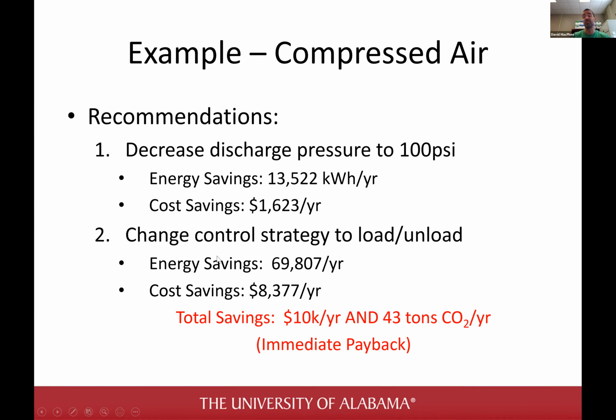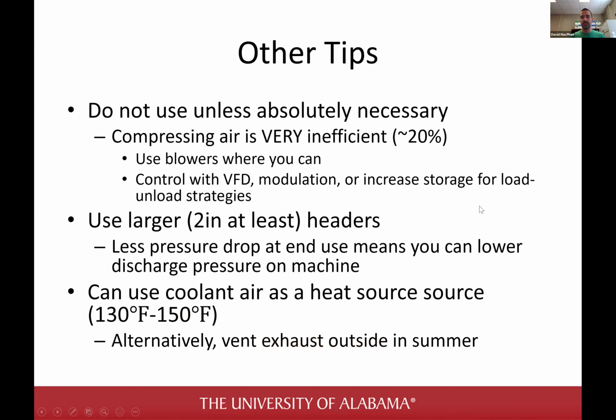Decrease discharge pressure, change control strategy. Another thing is decrease the leaks. Now, without seeing the facility, I can't really tell you how many leaks your facility has. There are a lot of facilities that have basically no leaks because they don't use a lot of valves or pneumatic tools, for example. But a lot of facilities do have a lot of leaks, and you can tell whether you have a lot of leaks in your facility, and you can probably decrease the amount of costs by 20% easily with an effective leak prevention program, just by going back every couple of months with an ultrasonic leak detector, which costs starting at about $500. They do get pretty expensive for the nice ones. Anyway, so this is an example. You could save $10,000 a year with these effective tips.